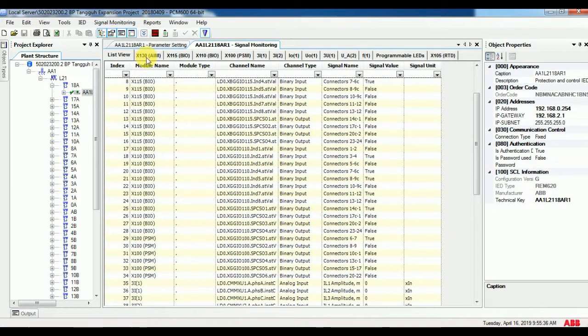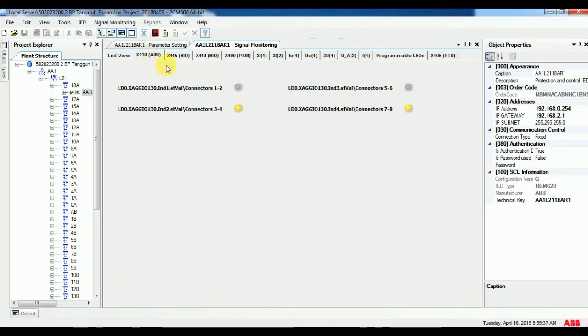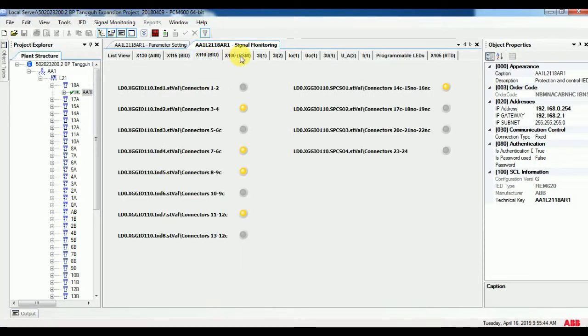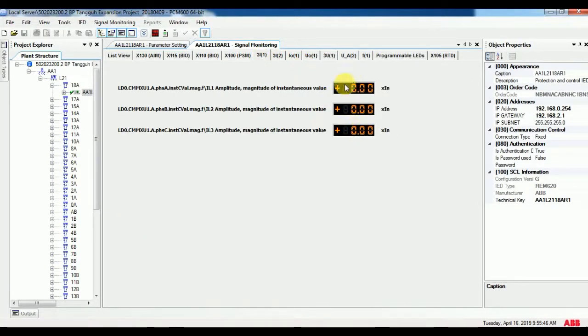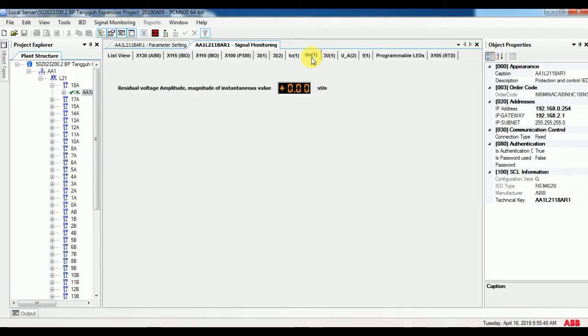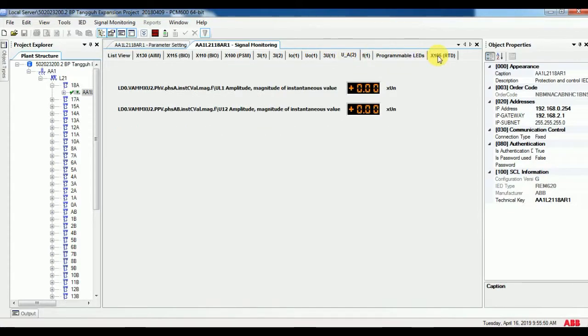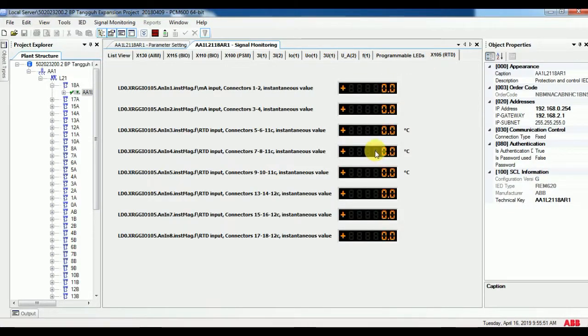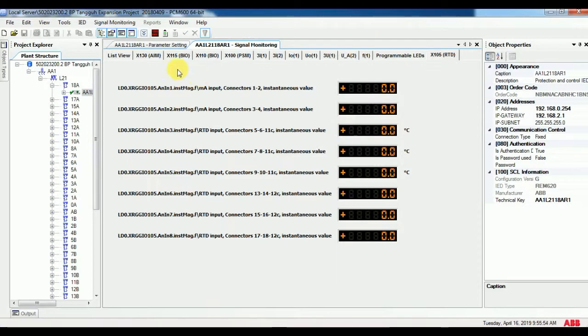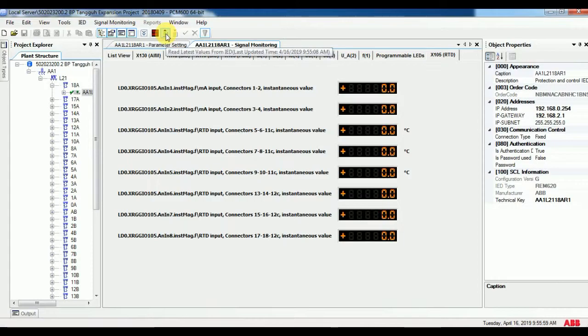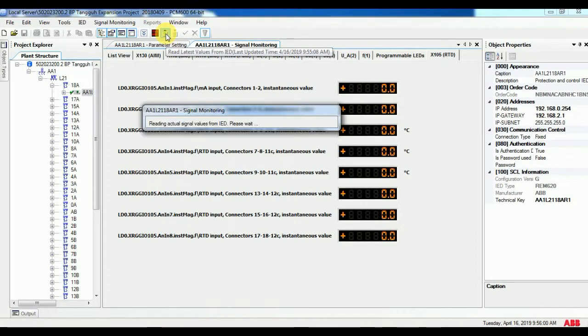Second, two methods of monitoring are possible. One is read last value from IED. It will be available on the top of the menu or under the IED menu. When you use it, it will read the value one time. If any changes occur, it will not show. You have to go for another one-time reading. Mostly this is not preferable.